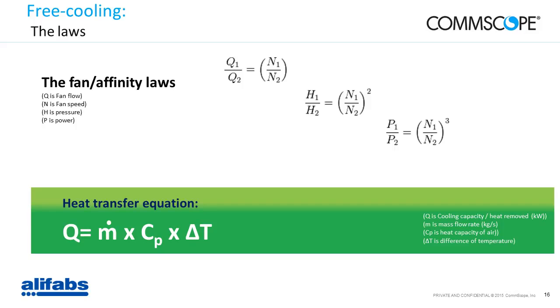So the heat transfer equation just gives us the good relation between the delta T, so the difference between the external temperature and the internal temperature of your site, the airflow, and the cooling capacity. And then you can just juggle with them. As long as you know at least two, you can then understand what delta T you can achieve or you need to achieve, what cooling capacity you can achieve or you will be able to achieve, and what airflow you need to be able to deliver.